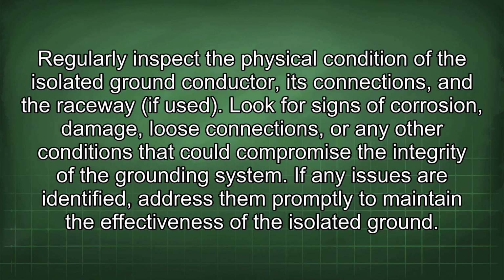Regularly inspect the physical condition of the isolated ground conductor, its connections, and the raceway if used. Look for signs of corrosion, damage, loose connections, or any other conditions that could compromise the integrity of the grounding system. If any issues are identified, address them promptly to maintain the effectiveness of the isolated ground.